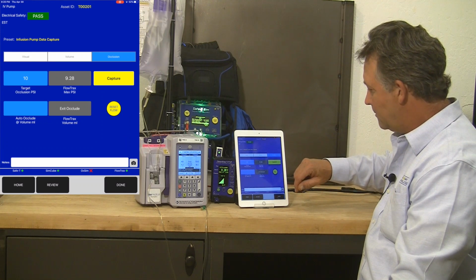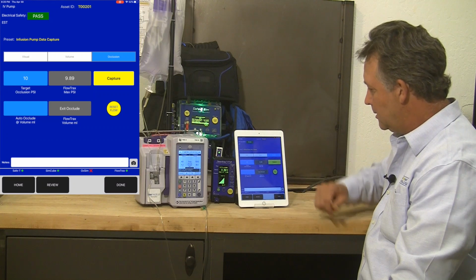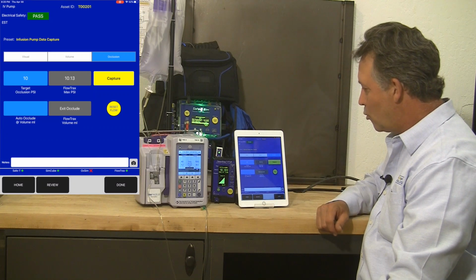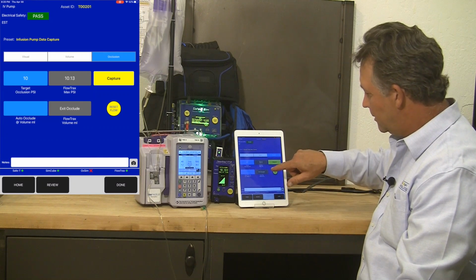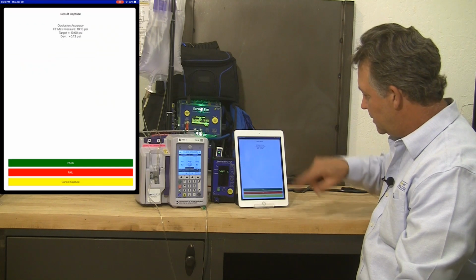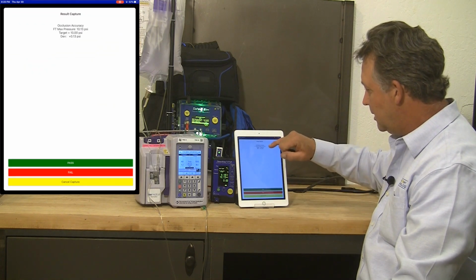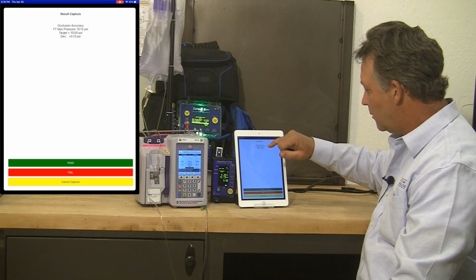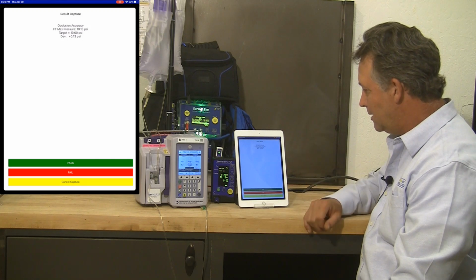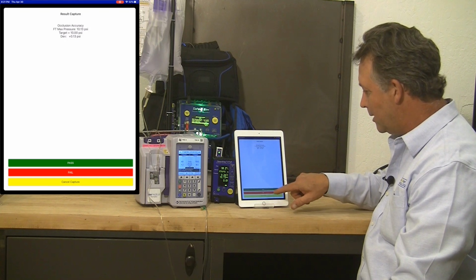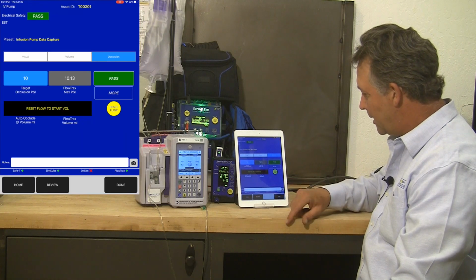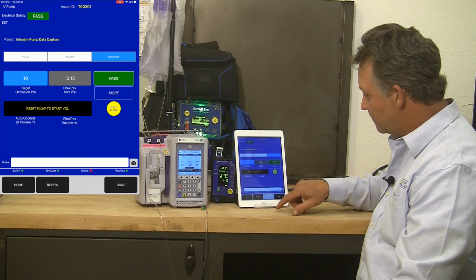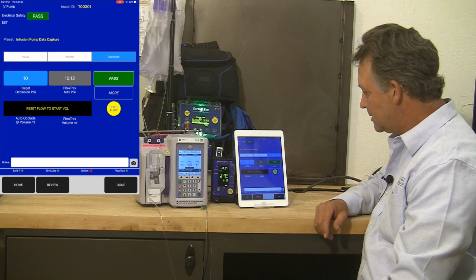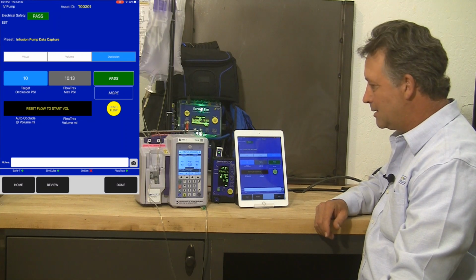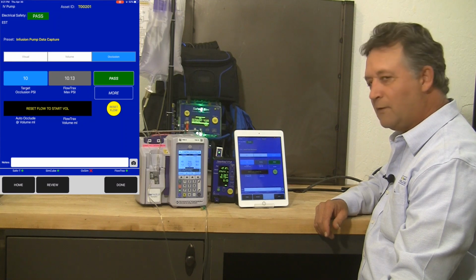We're right about 9 psi now. We can see that still climbing. 10.13. You don't get much better than that. Okay, so I go to capture. I see my max pressure was 10.13, target of 10, deviation of plus 0.13 psi. Clearly a pass. So I've completed my occlusion tests, both at 6 and at 10 psi thresholds on the IV pump. I'm ready to move on to my volume test.